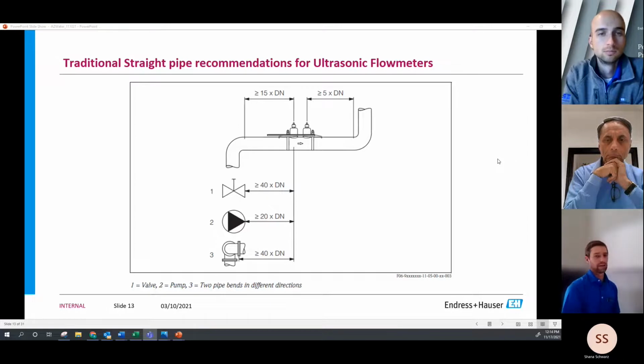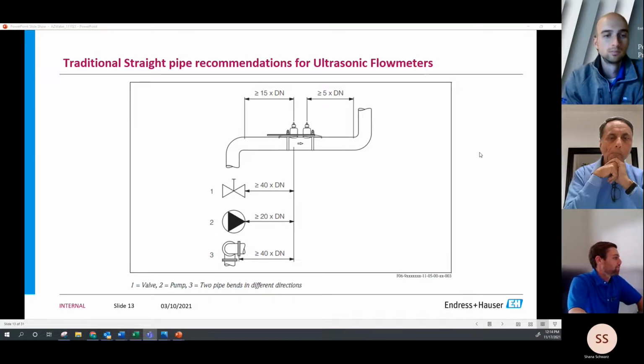And generally speaking, for clamp-on ultrasonic flow meters, you need quite a bit more straight run requirements. Convention being 15 pipe diameters upstream and 5 downstream. That's a lot of straight run. That can be a lot of cost for piping itself, not to mention the labor to install.